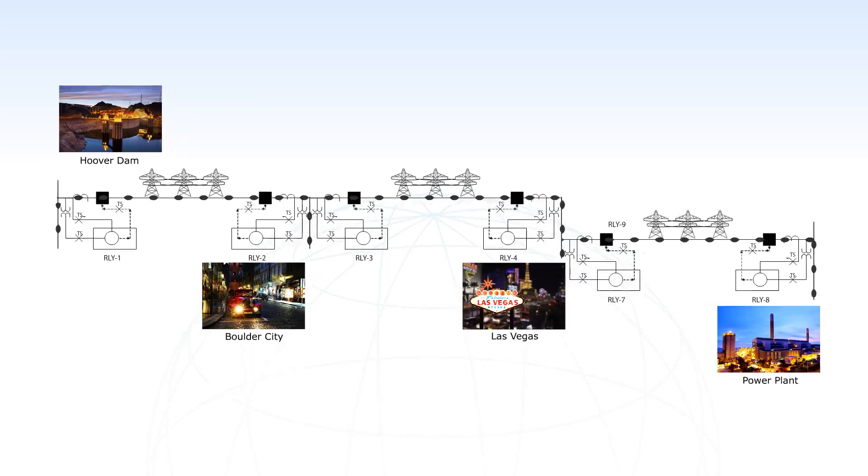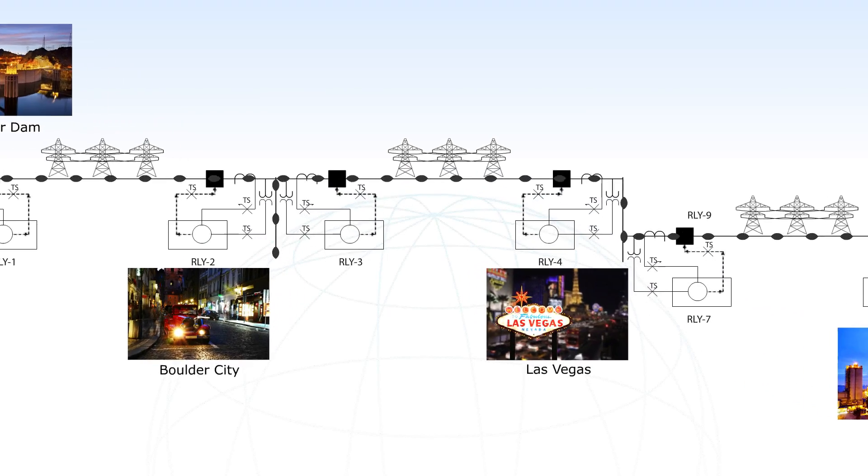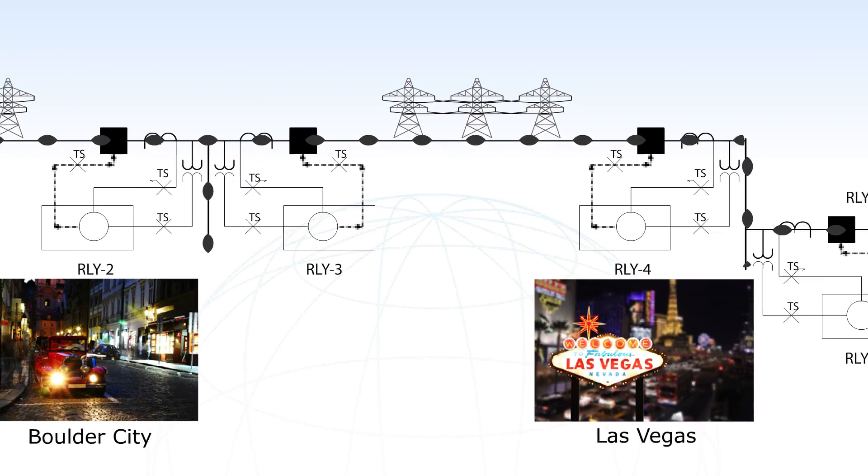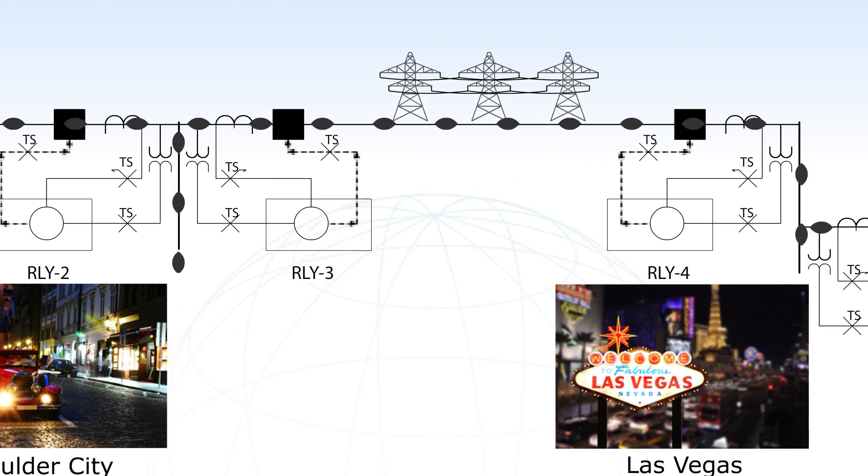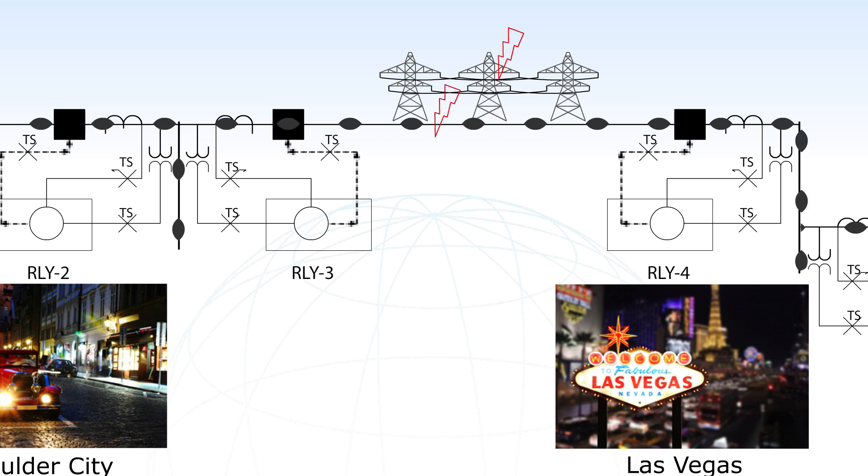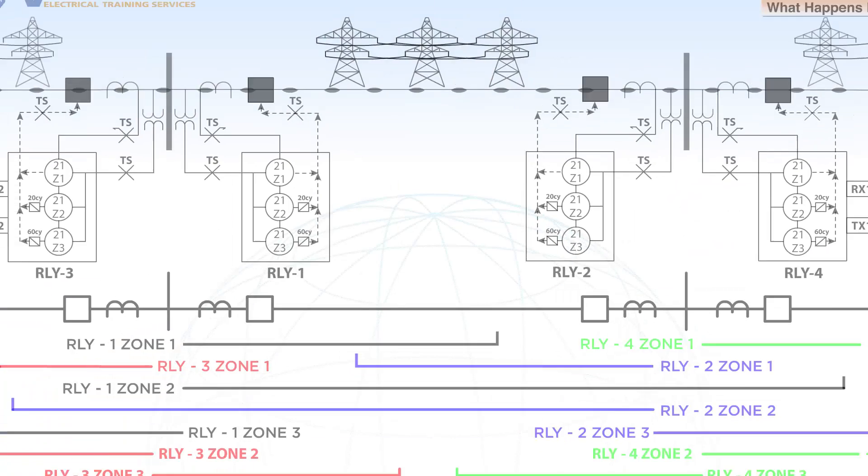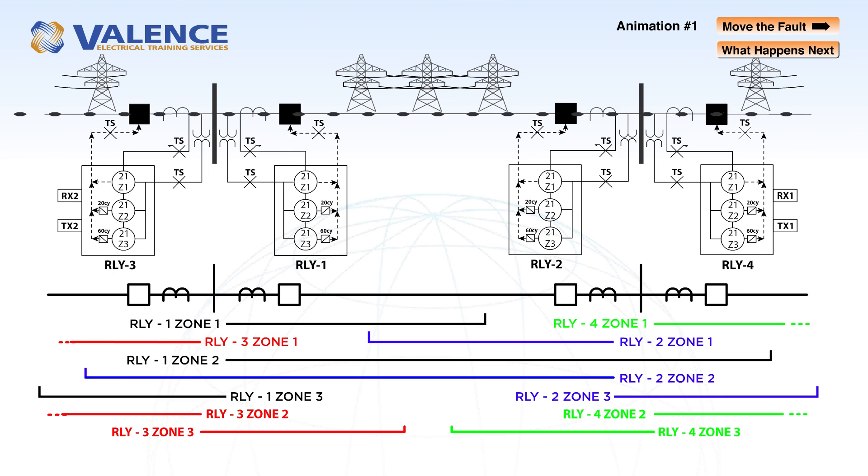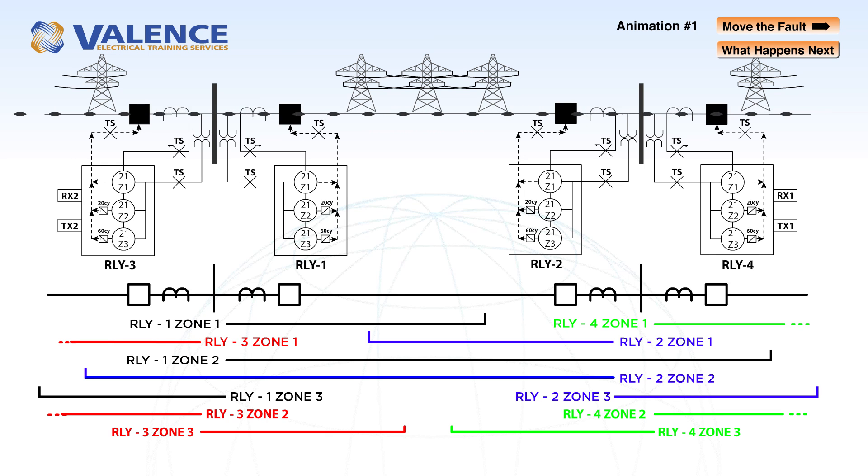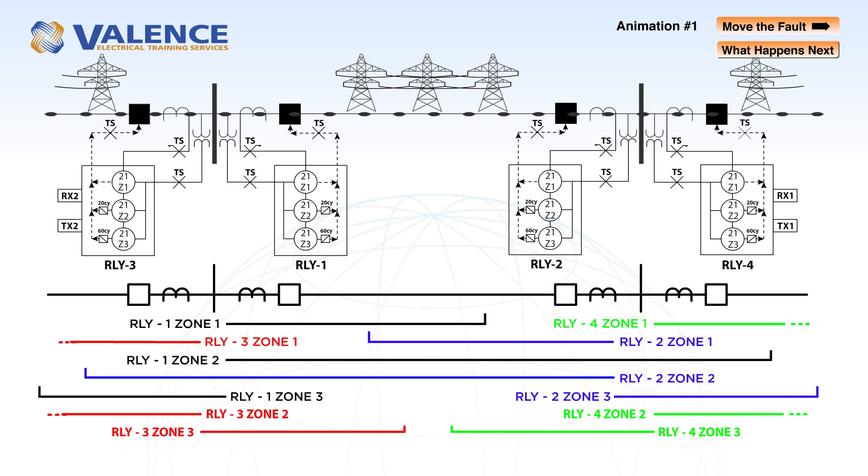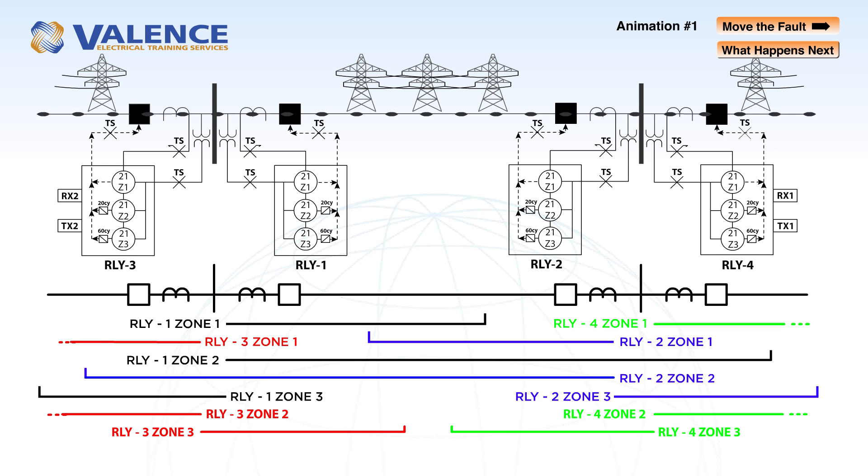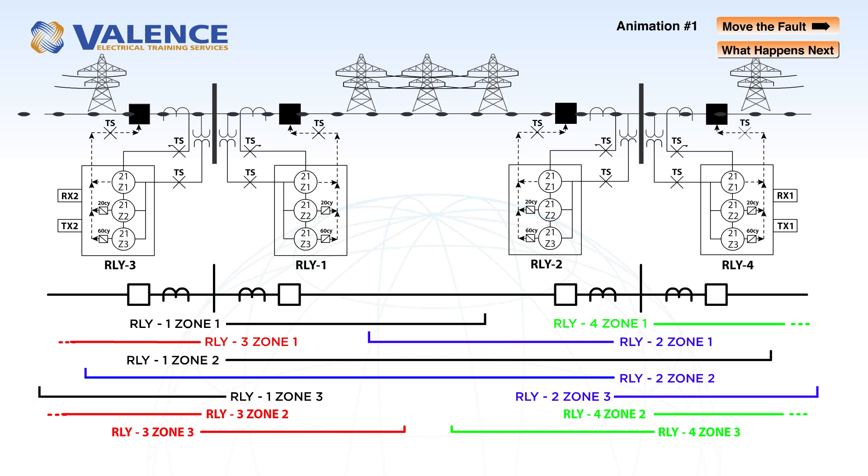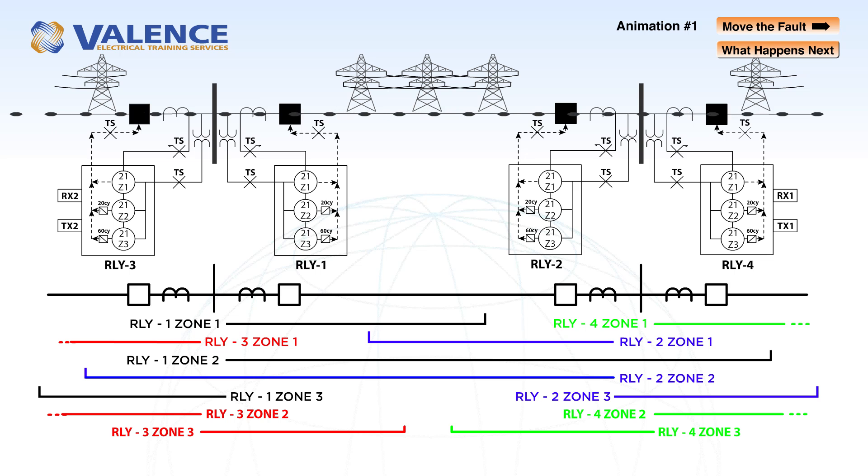Today, we're going to zoom in on one transmission line and see what happens when a fault occurs at different locations on the line. End-to-end relay testing plans typically apply a fault on either side of a protective zone to make sure that the relay operates correctly in each zone. We're going to apply the same series of tests that would normally be applied to a communication-assisted protection scheme to see what the two standard line distance relays will do in each scenario.